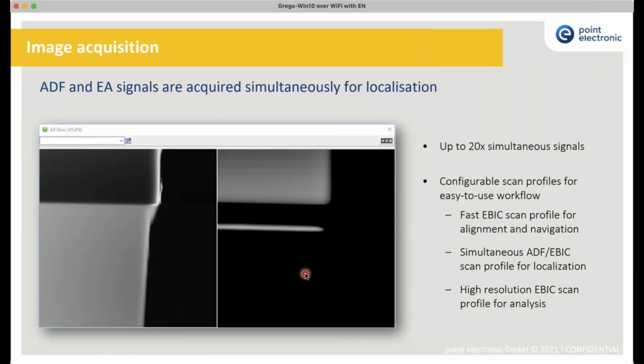But there are a few unique features that are very important for this kind of analysis, and one of them is being able to acquire signals simultaneously. And we really mean simultaneously, because we don't want images to drift or to be at a slightly different magnification. So we move the beam to one position, we digitize all the signals we want to digitize, and then we move to the next pixel position. In that way, we guarantee that when you mix these images, they will overlap in the same region.